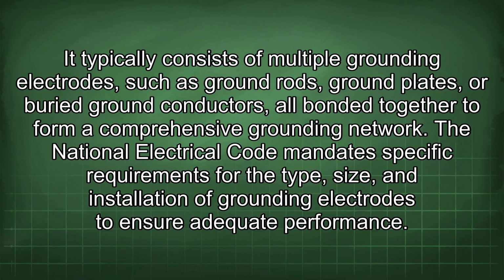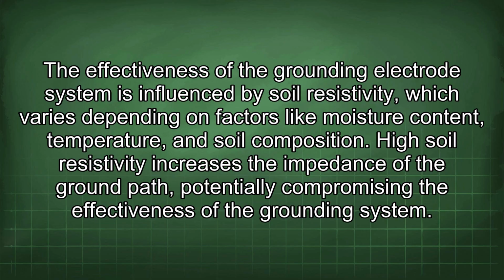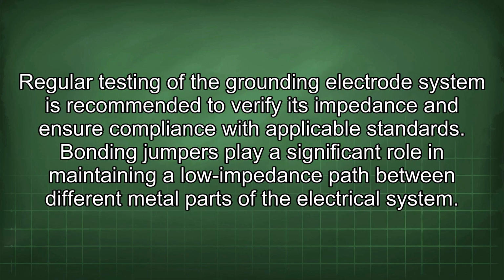The National Electrical Code mandates specific requirements for the type, size, and installation of grounding electrodes to ensure adequate performance. The effectiveness of the grounding electrode system is influenced by soil resistivity, which varies depending on factors like moisture content, temperature, and soil composition. High soil resistivity increases the impedance of the ground path, potentially compromising the effectiveness of the grounding system.